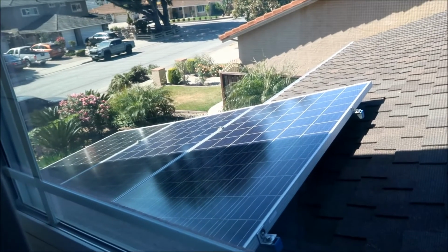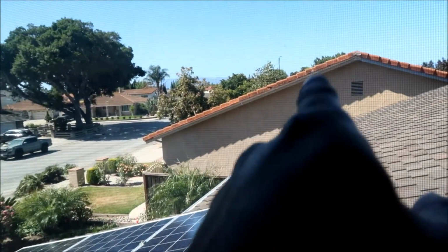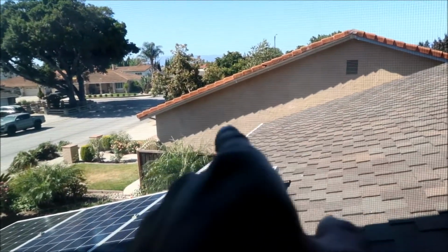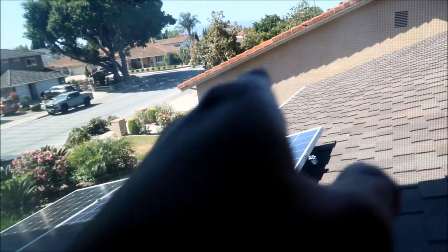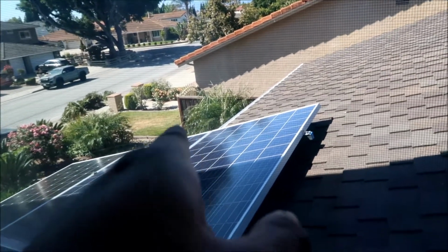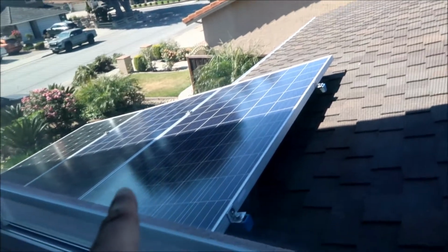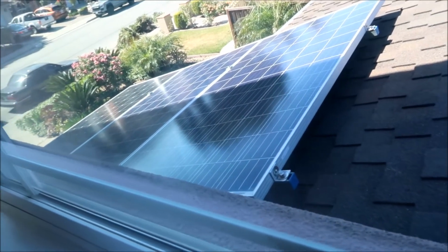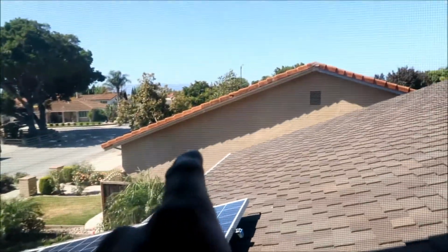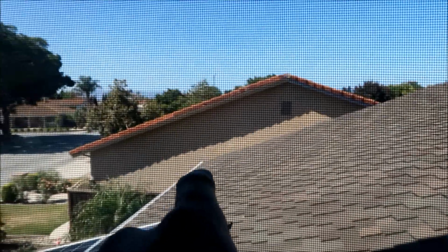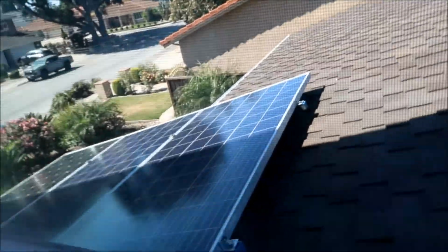Since all this stuff is up here already, all I've got to do is install the panels over there, put them in series, run an extension cord to the rail here, make a conduit that goes out here, and then use those branch connectors I bought and put it in parallel with this one. So when this one isn't making power, that one will. If I had solar panels over there, those would be making power right now. So that's a bummer. All right, here we go.